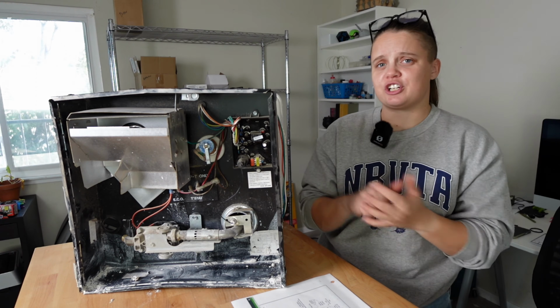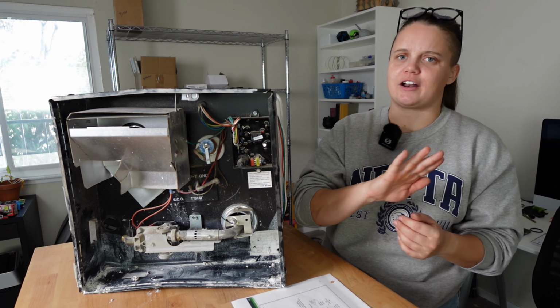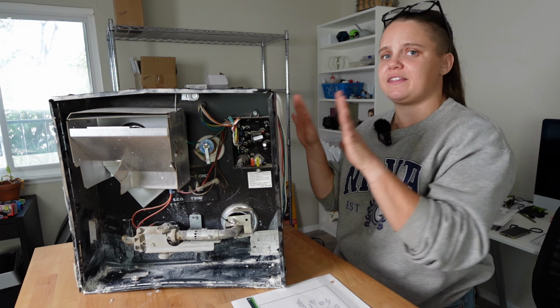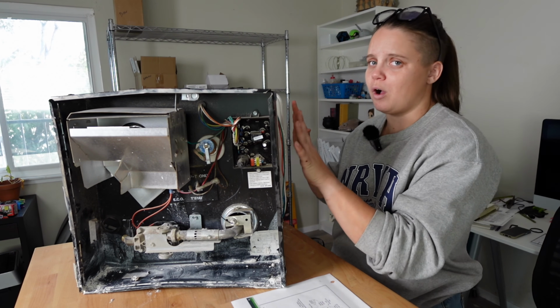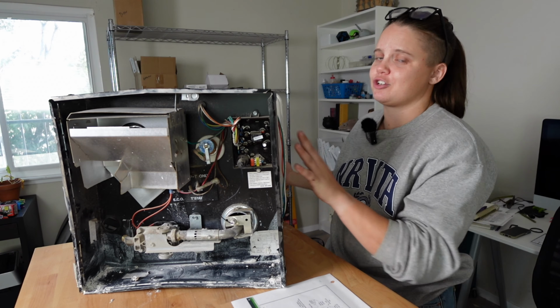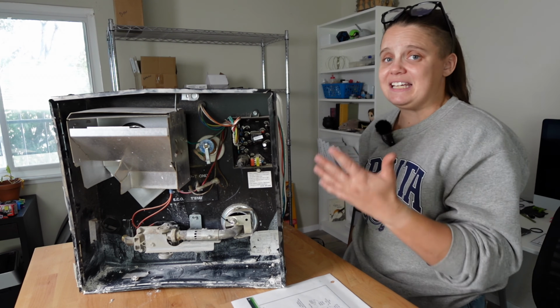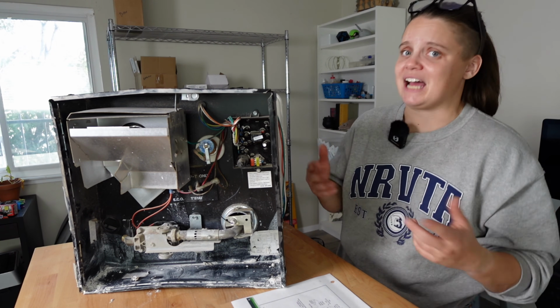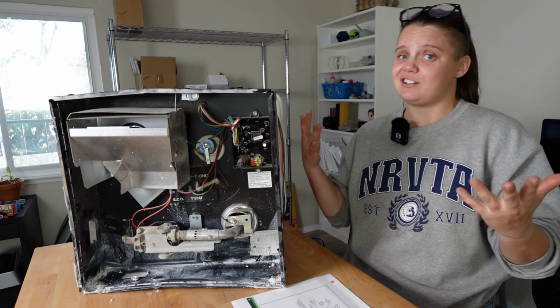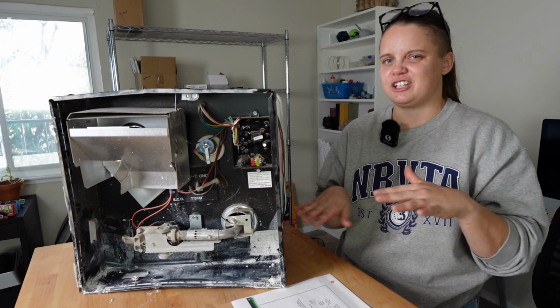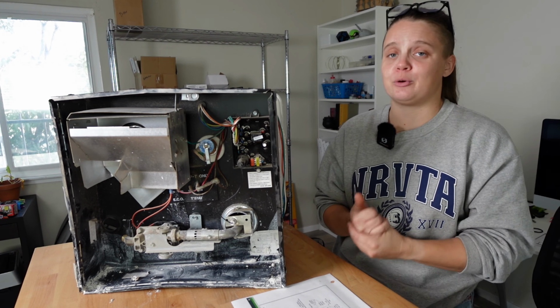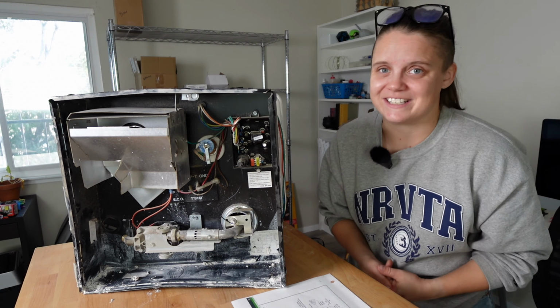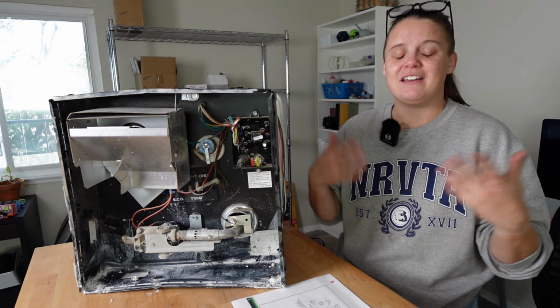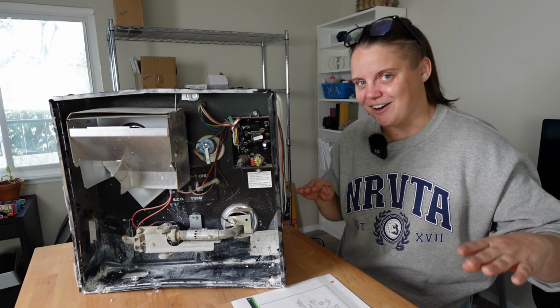The two things that we just checked, the Tstat and the thermal cutoff, are in place to make sure that this water heater isn't too hot before we go ahead and turn on the heating element. So the Tstat stands for thermostat. It's just checking to make sure, is this tank too hot? And if so, shuts everything down, doesn't let signal through. The thermal cutoff does something very similar, as you can tell from the name. If it gets too hot, it cuts off signal.